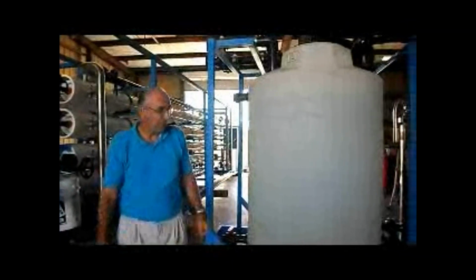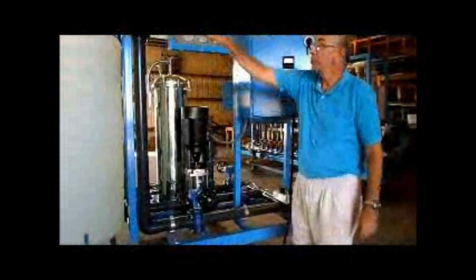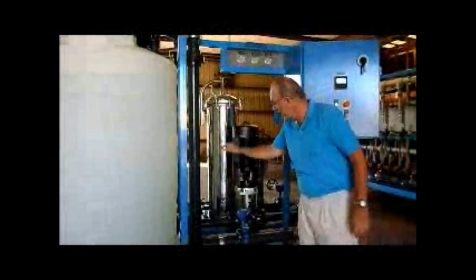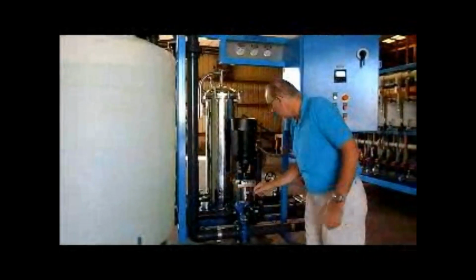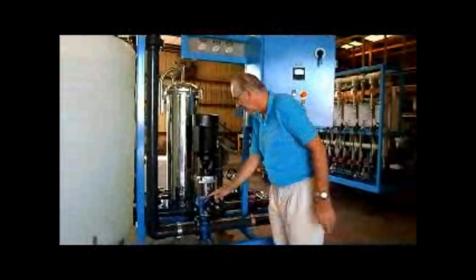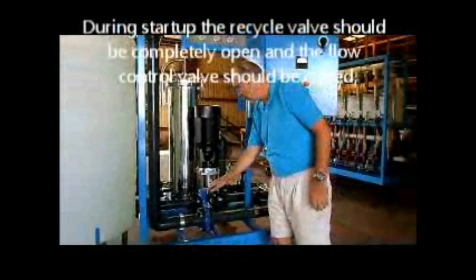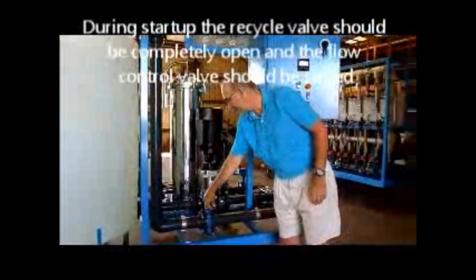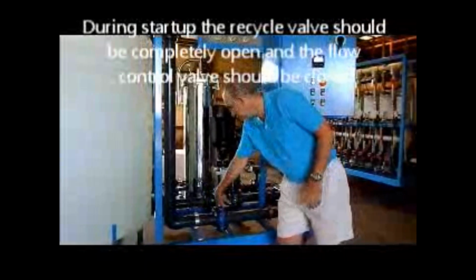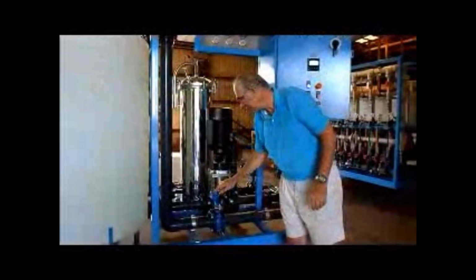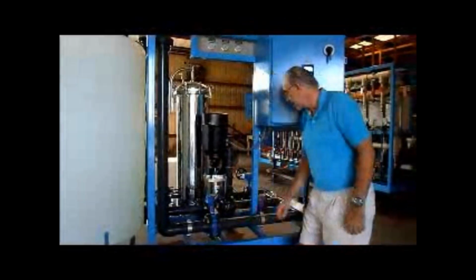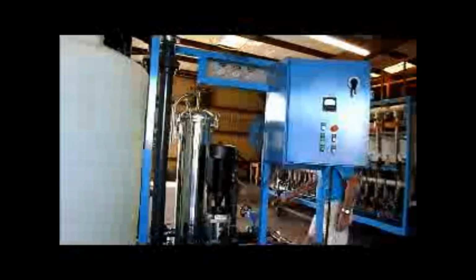That's all the valves. So let's review again. Normal operating mode, the two valves on top have to be open. The exit valve here is open, the suction valve into the pump is open, and these two valves are adjusted. Normally when startup, we will open this one completely, and we will close the flow control valve completely. Open this, close this.